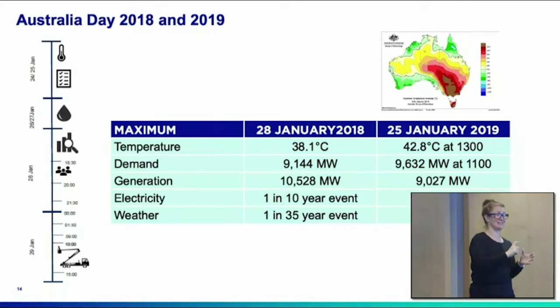On the 28th of January, there was enough electricity to meet that demand. You can see in the table that we wanted over 9,000 megawatts of demand, and there was 10,500 megawatts available. The problem was that we were trying to shove so much electricity down the wires that the protection equipment, the surge arresters and the fuses, activated to keep us safe, because you don't want your lines to get too hot. As a result, 95,000 people lost power.